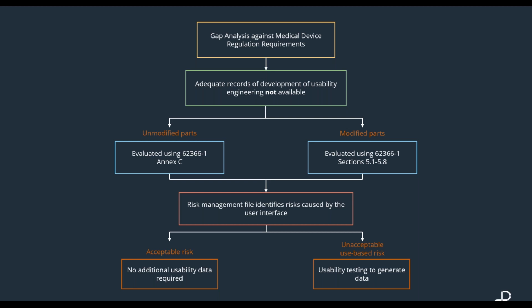And you then have a look and you say, right, okay, well, these are the things that we're going to need in place. So everything that you've got in your legacy part of the product, you're going to need to have in place a use specification, all your post-market information, so whether any complaints, existing use data, any hazards or hazardous situations that are associated with usability, any risks associated with usability, and an idea of what your overall residual risk will be.